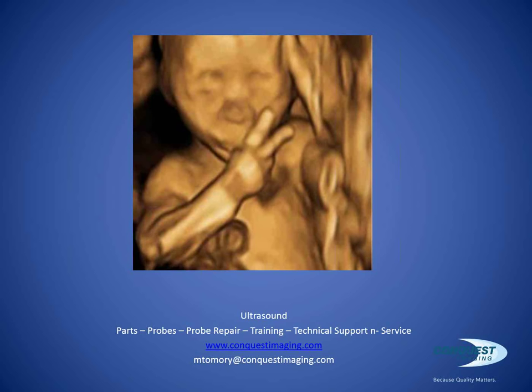Excellent. The next question is, is there a required phantom for ACR accreditation? There's not, and that's where ACR gets a little tricky. ACR asks you to do sensitivity measurements with an ultrasound probe. So they say pick a probe, any probe, and they want you to do sensitivity testing. So they want to know how far or how deep that probe is penetrating. Well, unless you're adept at scanning yourself and can truly do that and find the noise floor on your own body, you need a phantom. But yet there's a section in their annual evaluation that says the phantom is optional. So they're making you do a test that probably in all likelihood would require a phantom, but then they tell you a phantom is optional.